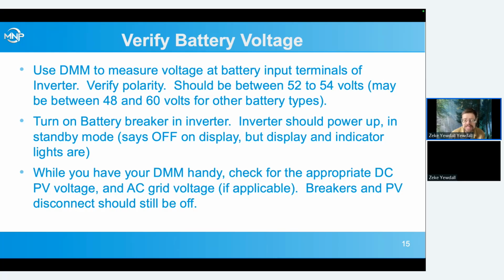It'll power up in standby mode. It says off on the display, but the display and the indicator lights are on. So usually when we're saying the inverter is off, it's actually in standby. Completely off is with the battery breaker off and all power off, and there's nothing on the display. But standby is where we do all of our programming, and it does say off on the display, but the display is on.